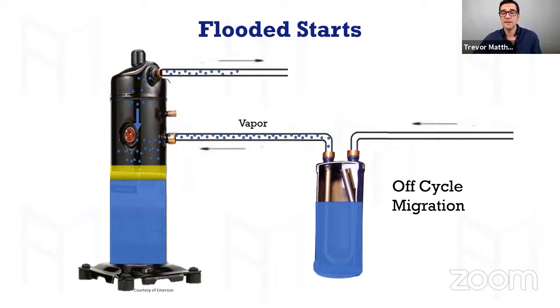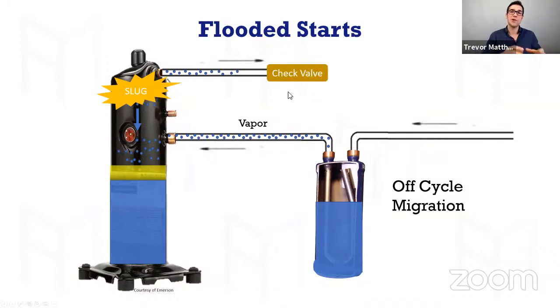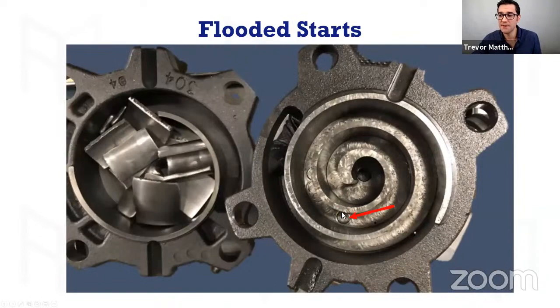And then once again, if the compressor is off, depending on how much refrigerant is in the specific compressor and the specific application, it could be coming back through your discharge line out of your high side. And bam, you get a flooded start or a slug. You may need a check valve. So this is why it's so important to go to those compressor manufacturer guys and find out: if I have 7 pounds or 10 kg in my system, do I need a check valve on my discharge line or not? This is the research you need to do as a technician. Boom, because this is what happens. This is a flooded start.